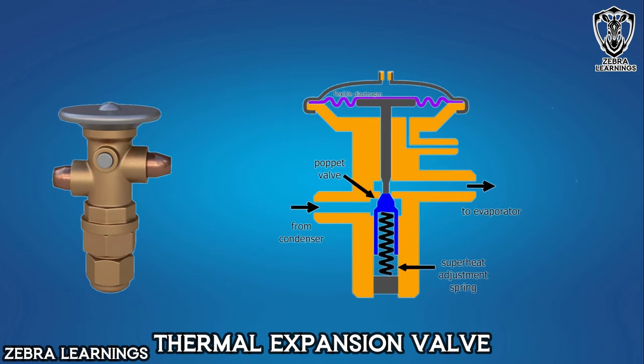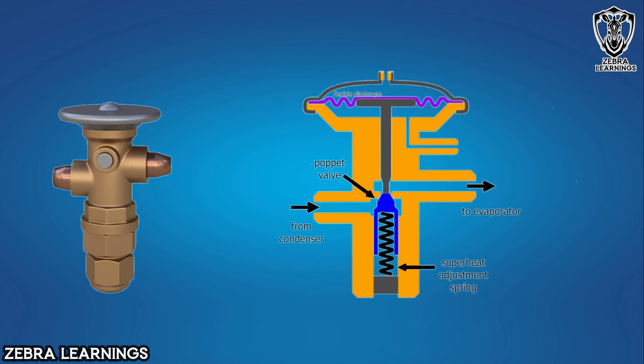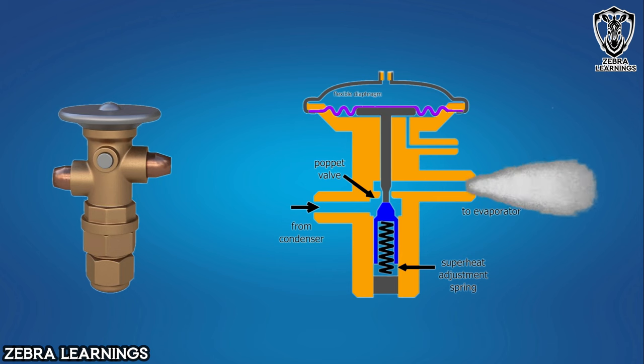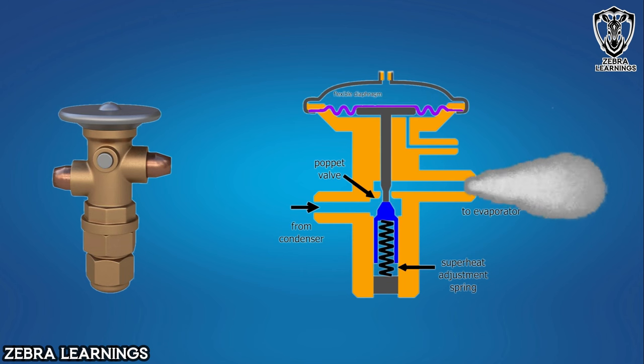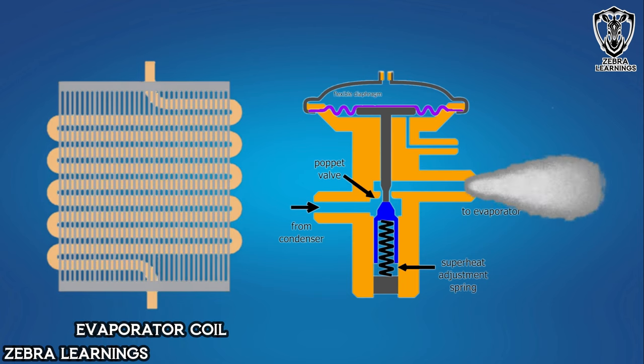The thermal expansion valve can also be a cause of evaporator coil freezing. The thermal expansion valve sends the required refrigerant to the evaporator coil. It sends more refrigerant when needed and less refrigerant when not needed. If the thermal expansion valve does not close properly, it will send too much refrigerant to the evaporator coil. So, the evaporator coil gets overcooled and freezes.